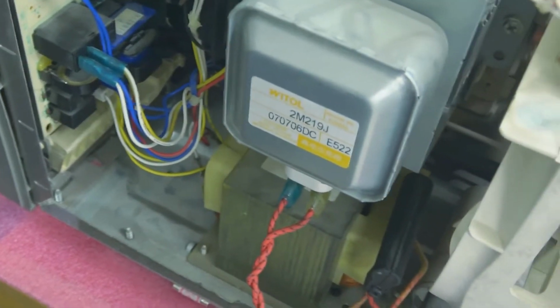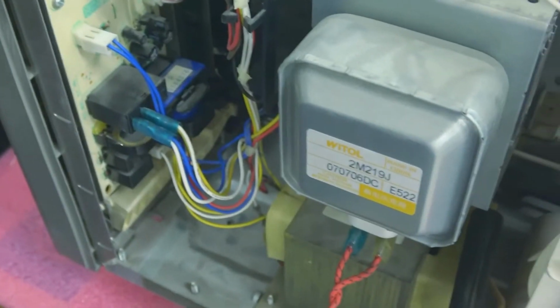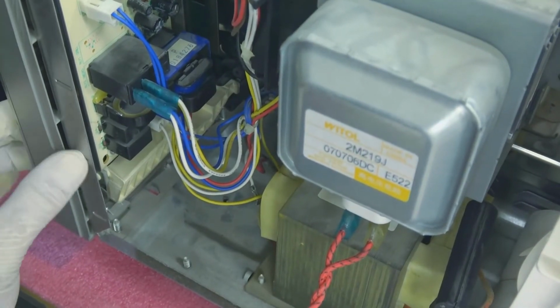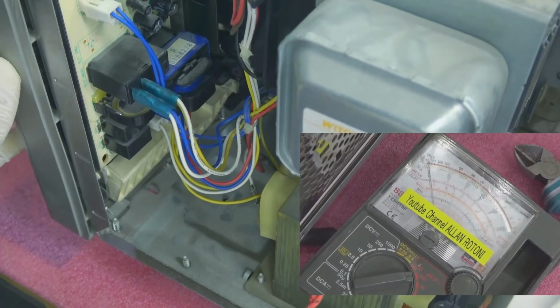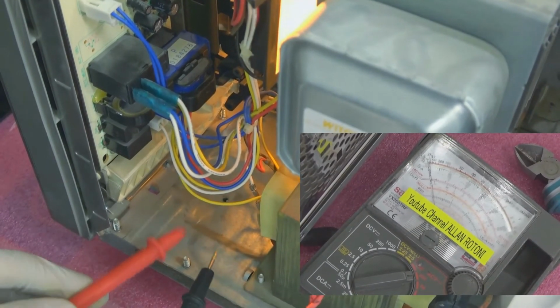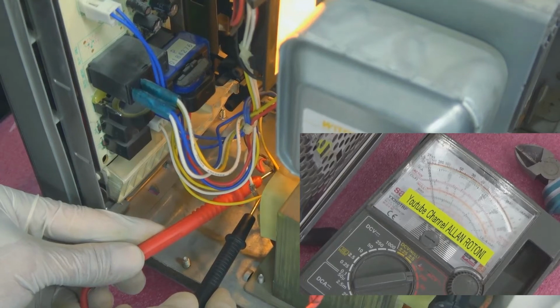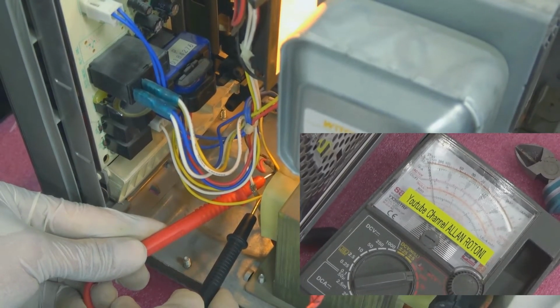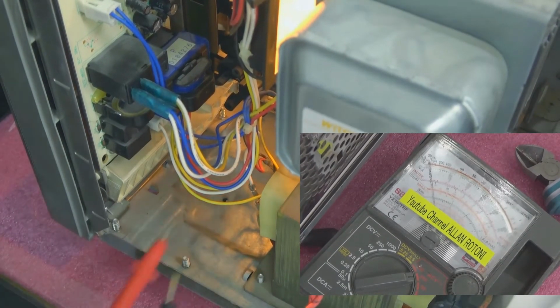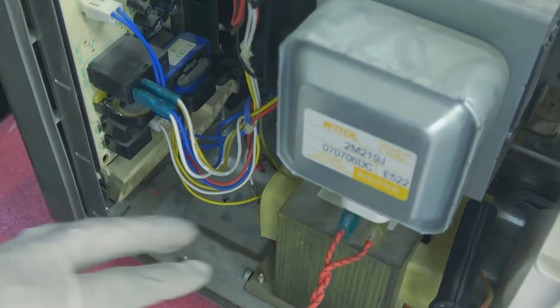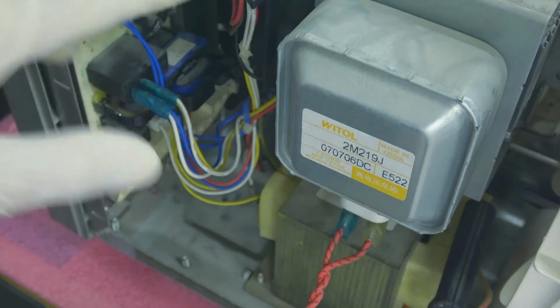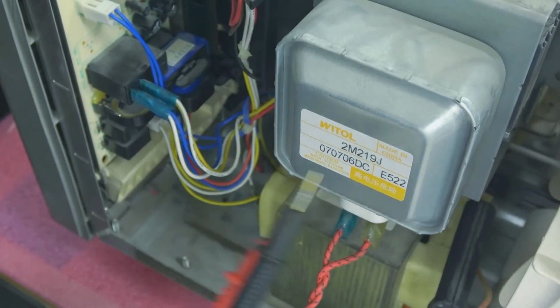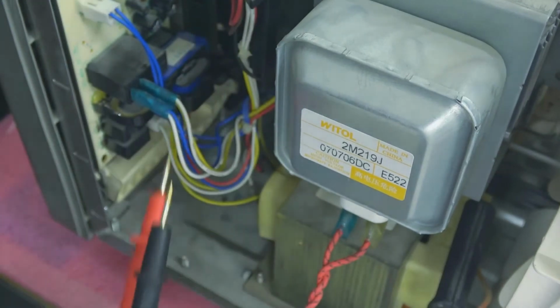I am going to check the primary transformer, the input, if there is a supply running on it. I will turn on the unit now. Start and check the primary supply, and primary supply is not there. There is no supply. So stop. If there is no supply, meaning there is a faulty line on this side, the door switch, and we are going to trace that one.